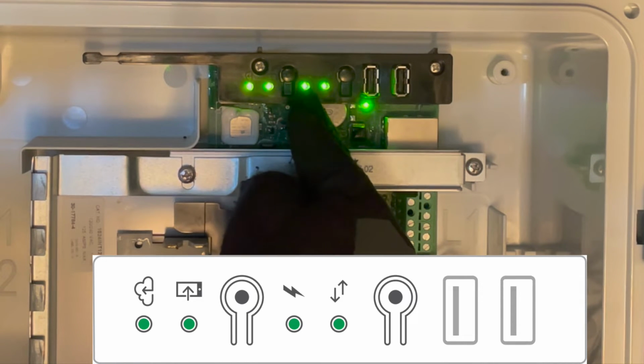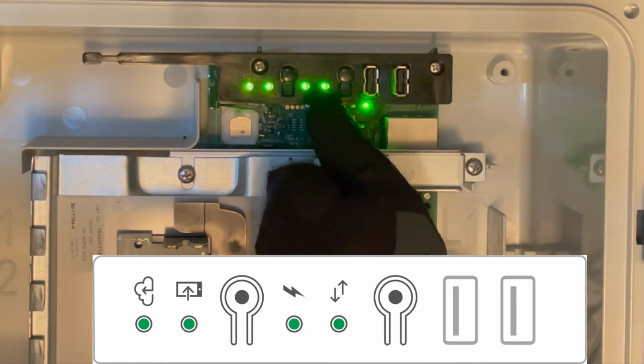The lightning symbol indicates that the microinverters are producing power. Note that initially it can take some time to light up green as the system needs the microinverters to report in. The arrows symbol indicates if the microinverters are communicating with the gateway. Again, it can take some time for this to turn green after the system is turned on. The microinverters need to be provisioned and need to report in to the IQ Gateway.